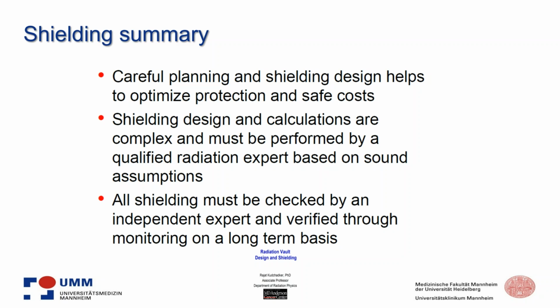This shielding summary is a very good example from the presentation of Professor Kuchaka. Careful planning and shielding design helps to optimize the shielding design, and the calculations are complex and must be performed by a qualified radiation expert, and the shielding must be checked by an independent expert to monitor on a long-term basis.